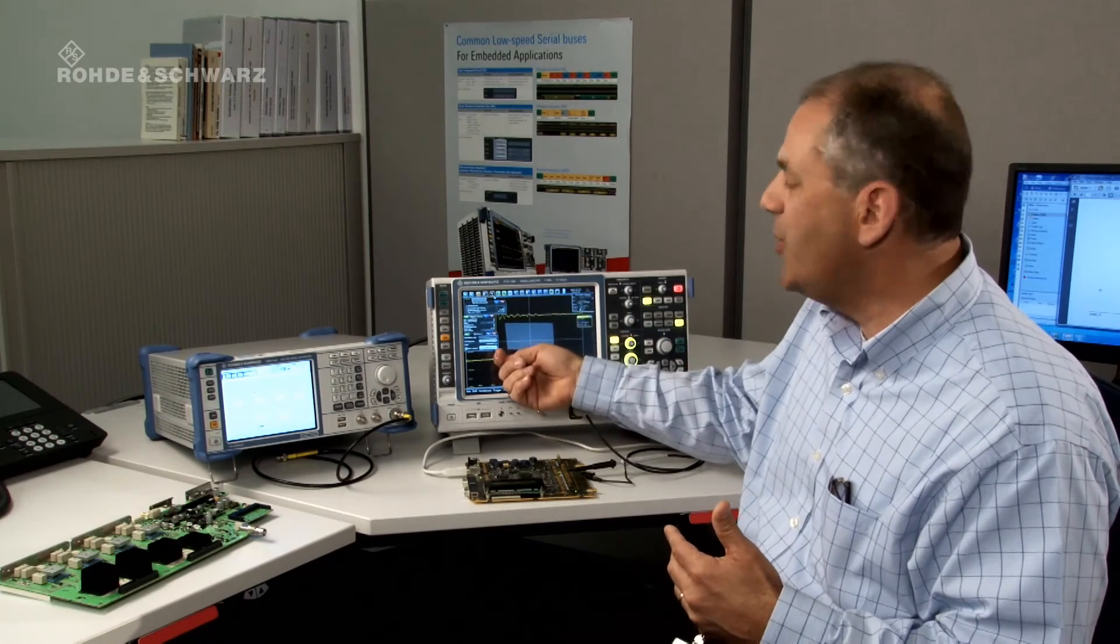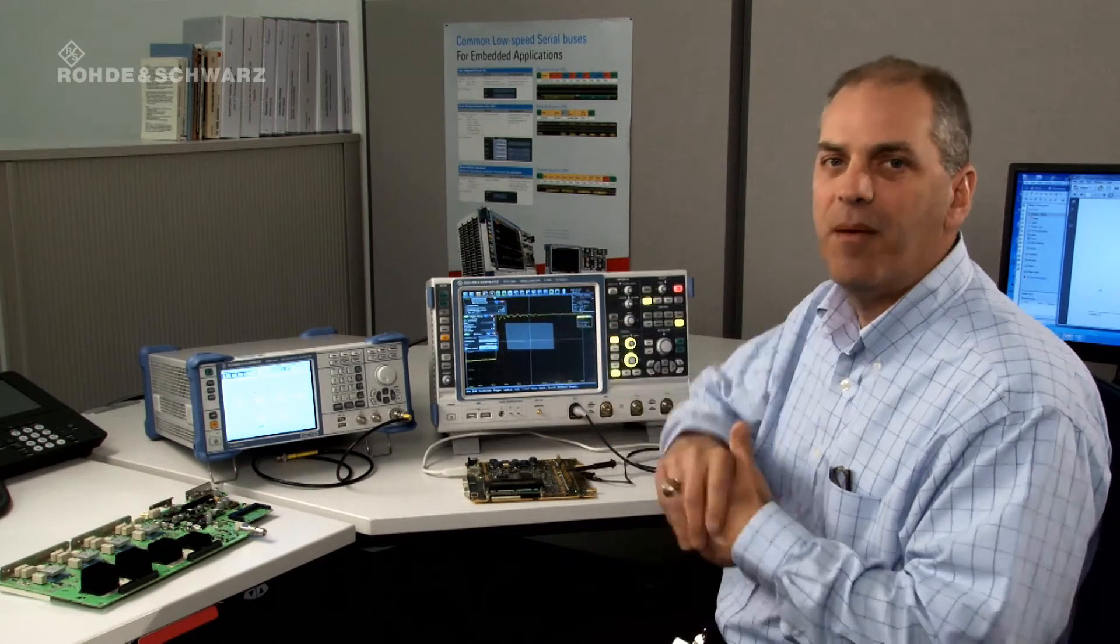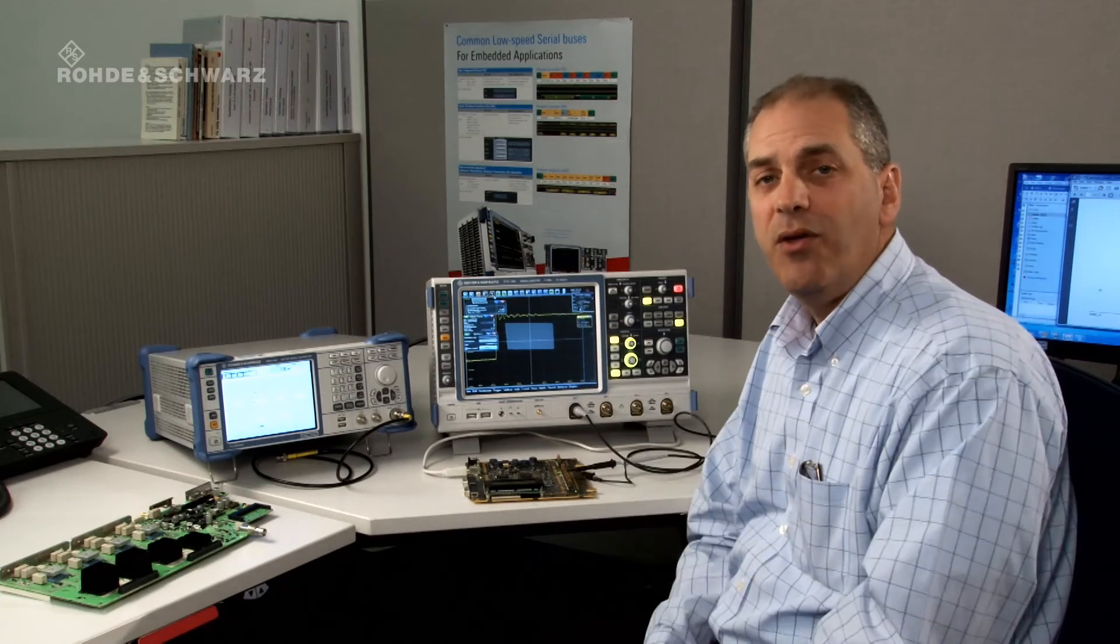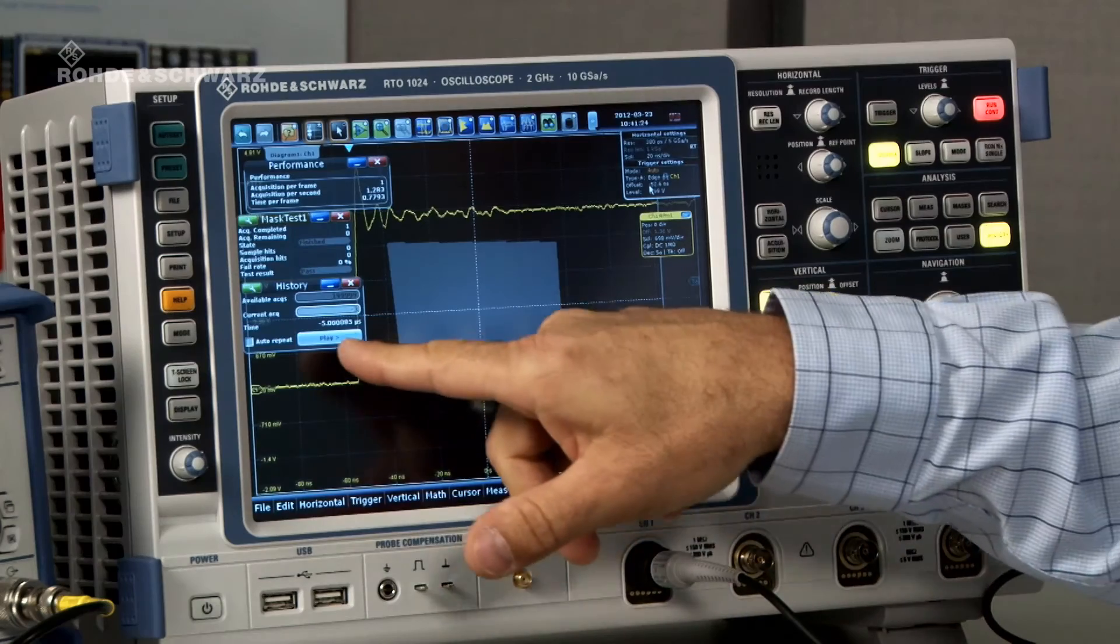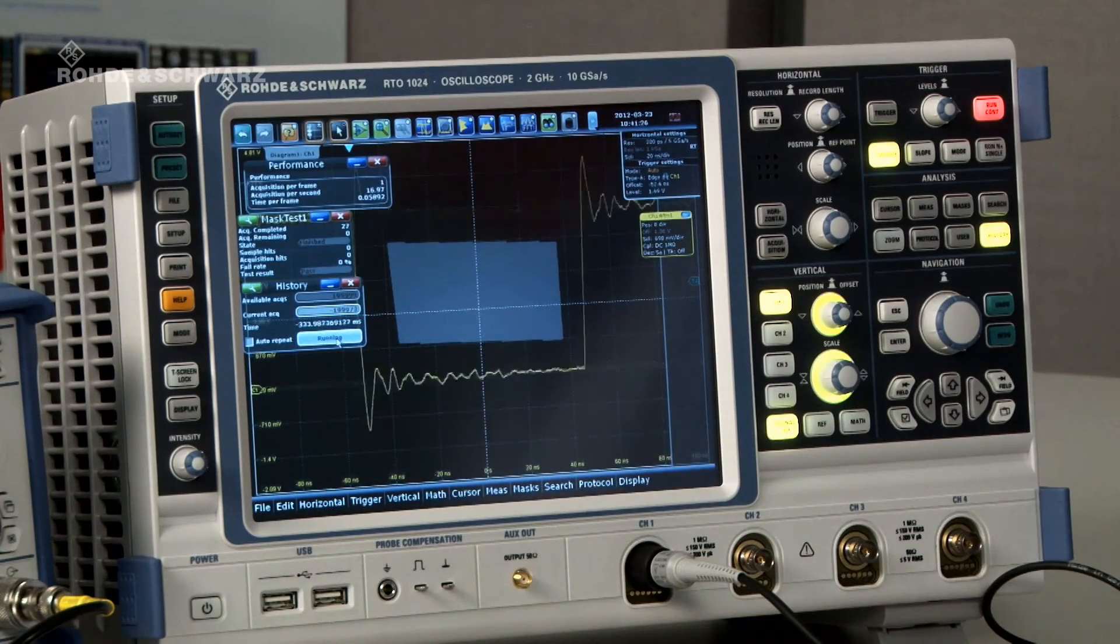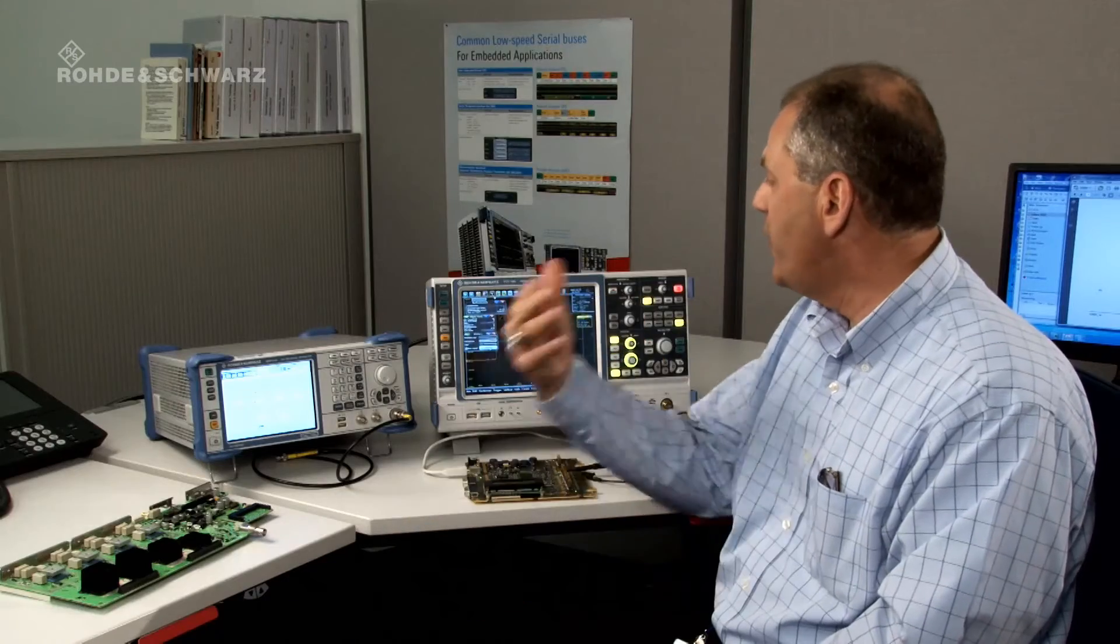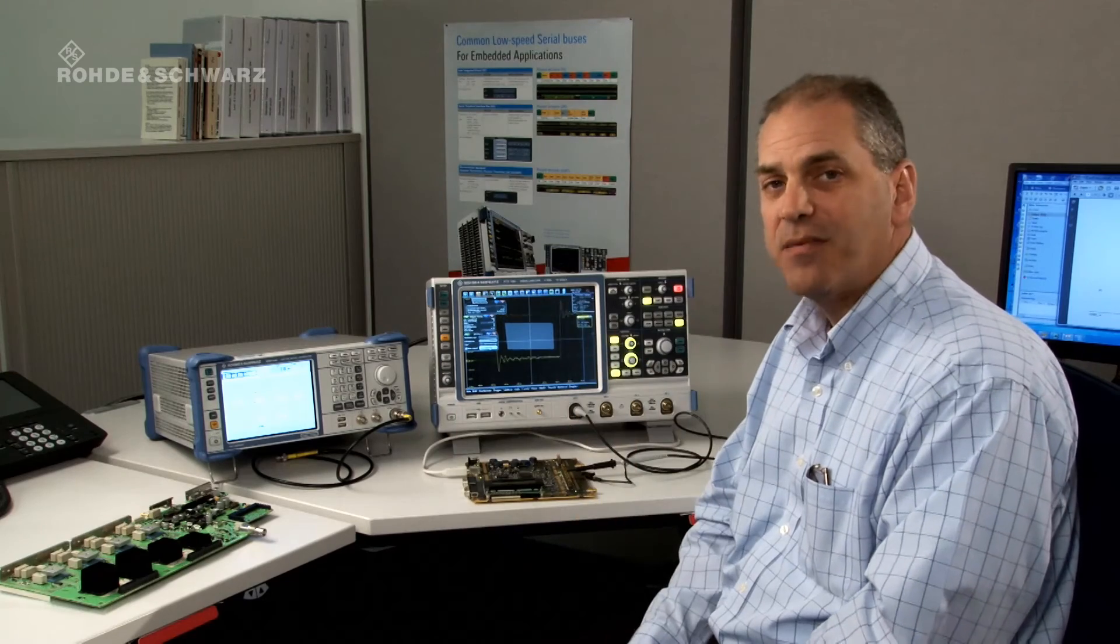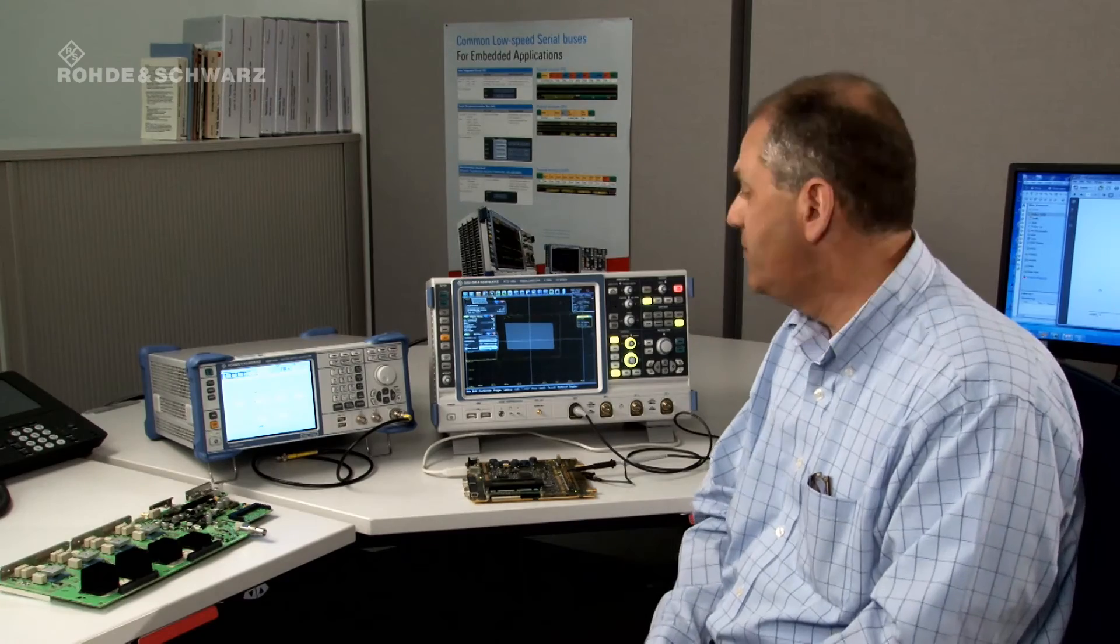You can also play the data back kind of like a tape recorder and just watch the recorded waveforms as they go past the mask. And the speed of this recording can be varied from second per update to milliseconds per update. So you can actually page through the data very, very slowly.